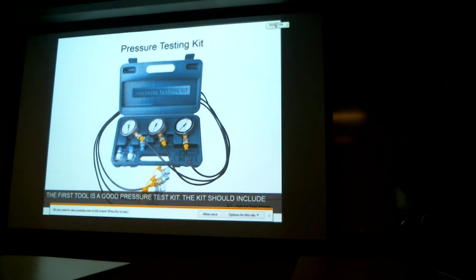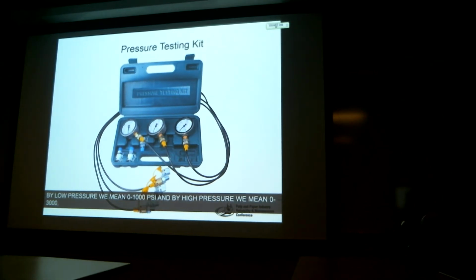The first tool is a good pressure test kit. The kit should include at a minimum one low pressure and one high pressure gauge. By low pressure we mean 0 to 1,000 psi, and by high pressure we mean 0 to 3,000. Of course, some systems will operate at a high enough pressure to need a 0 to 6,000 psi gauge. Small hoses and fittings should be included so that the gauges can be mounted wherever they're needed.